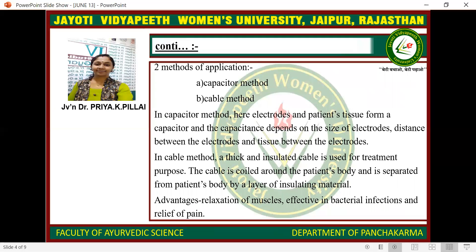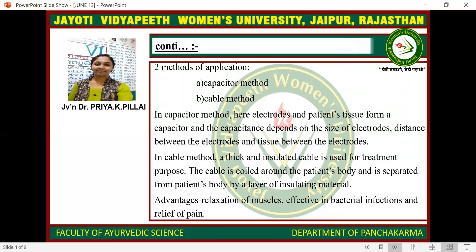Two methods of application: the capacitor method and the cable method. In the capacitor method, the electrodes and patient's tissue form a capacitor, and capacitance depends on the size of the electrode, distance between the electrodes, and tissue between the electrodes. In the cable method, a thick insulated cable is used for treatment; it is coiled around the patient's body and separated from the body by a layer of insulating material.